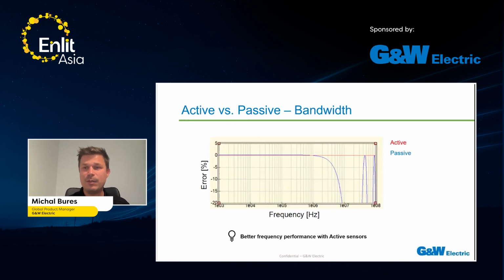The last, but I would say maybe the most important one, is the bandwidth. As you can see in the chart, the active sensor provides much higher frequency measurement bandwidth without losing accuracy. So it's a perfect solution for measuring harmonics and superharmonics. This is the topic we are discussing also today. Plus, we are using capacitive dividers, which provide much better frequency response even without the electronics. So this is what you can remember, maybe make a note: the combination of the capacitive divider plus the active sensor is probably the best variant available on the market for high frequency measurement, for detection of superharmonics and for power quality measurement.